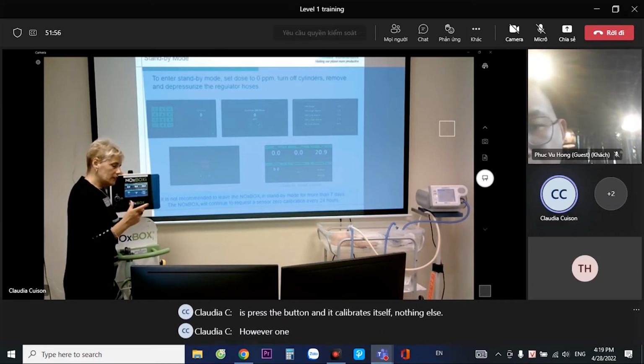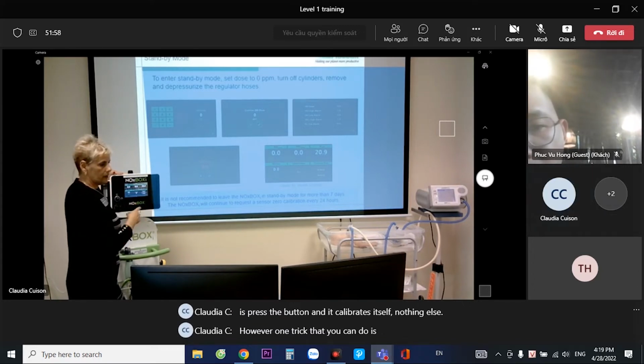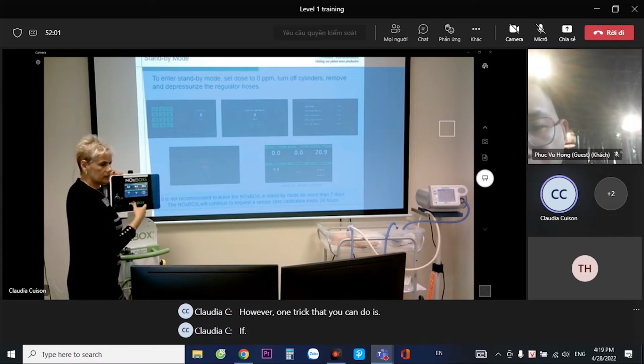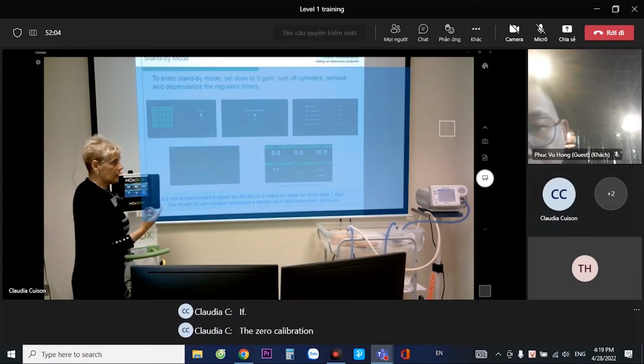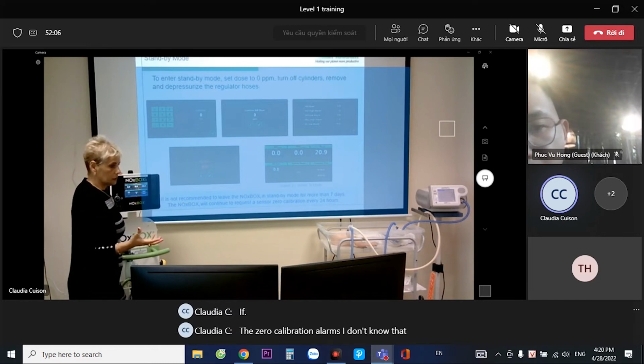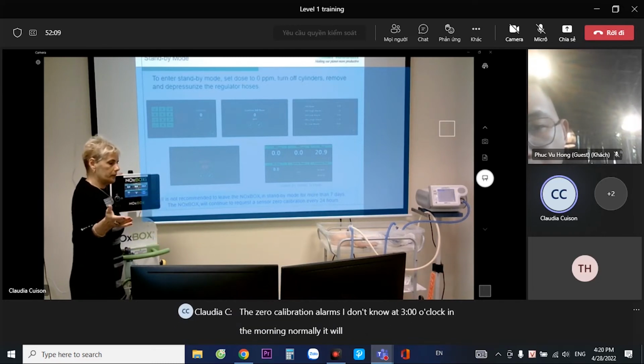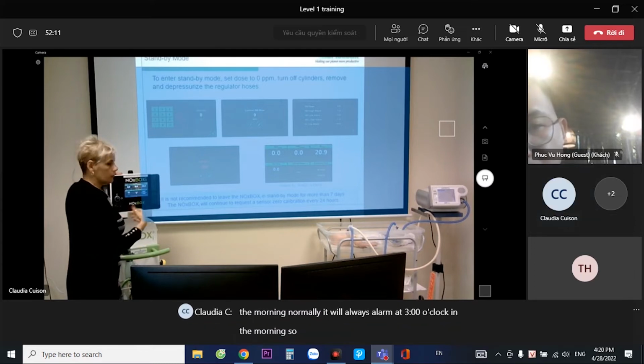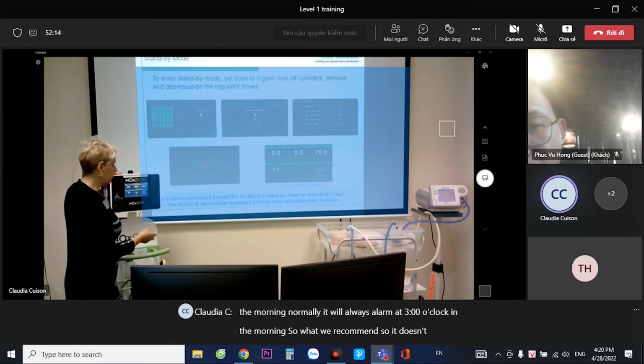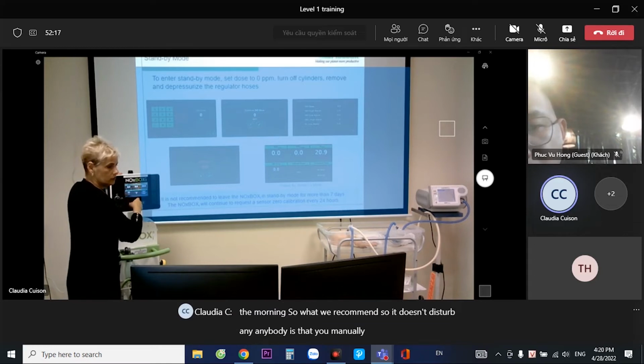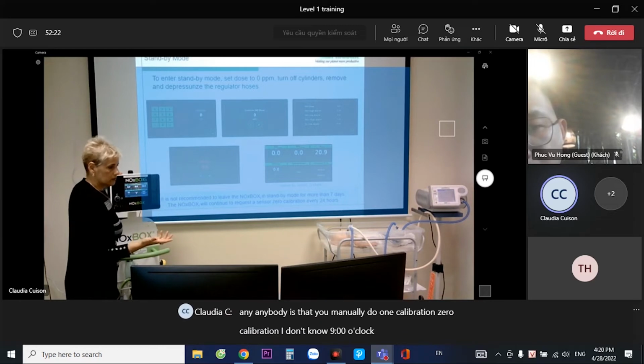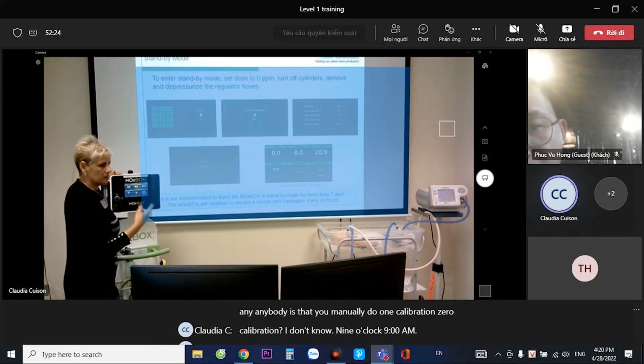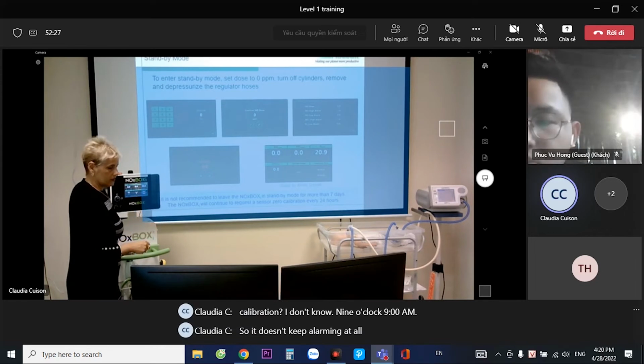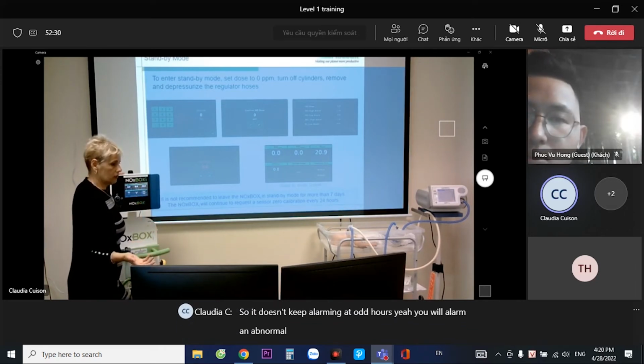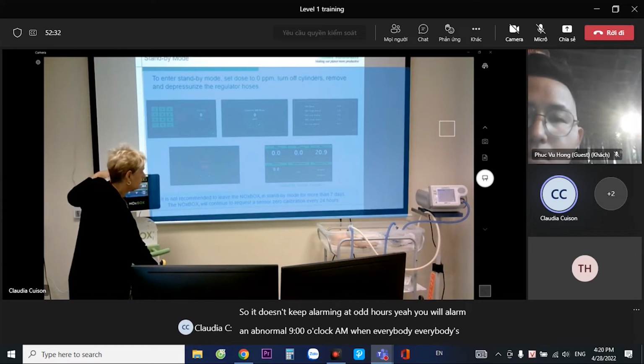However, one trick that you can do is, if the zero calibration alarms, I don't know, at 3 o'clock in the morning, normally it will always alarm at 3 o'clock in the morning. So what we recommend, so it doesn't disturb anybody, is that you manually do one zero calibration, I don't know, at 9 a.m. So it doesn't keep alarming at odd hours. Yeah, it will alarm at a normal 9 o'clock a.m. when everybody's there and doing their rounds.